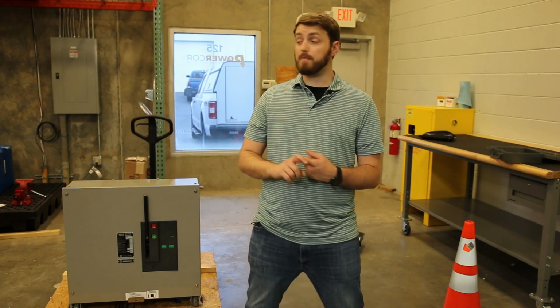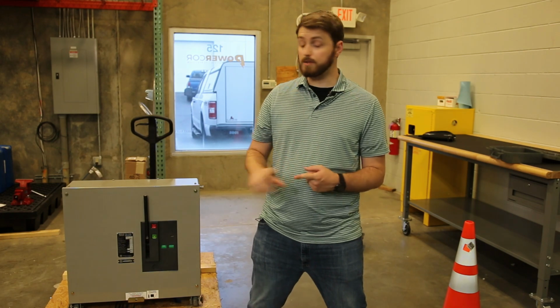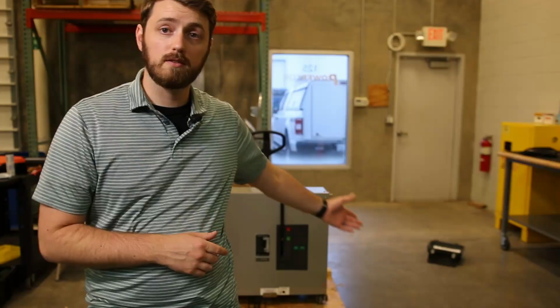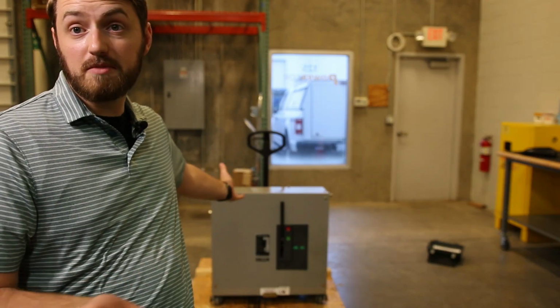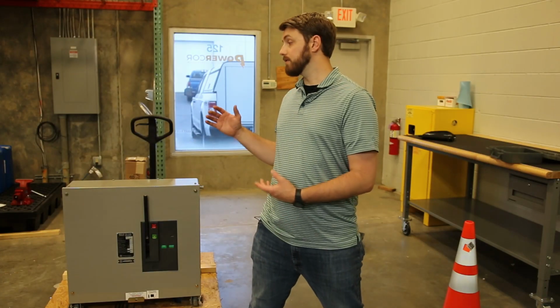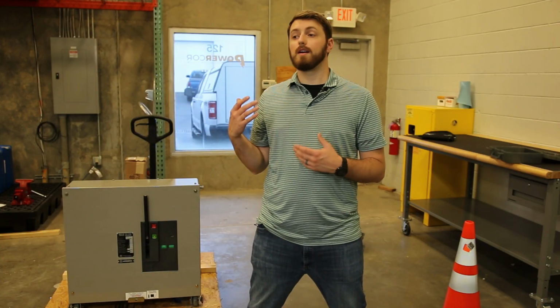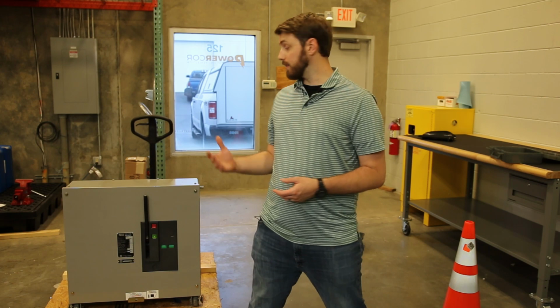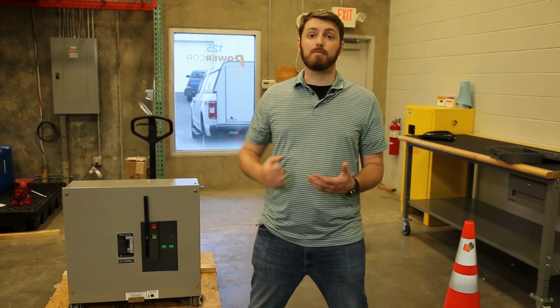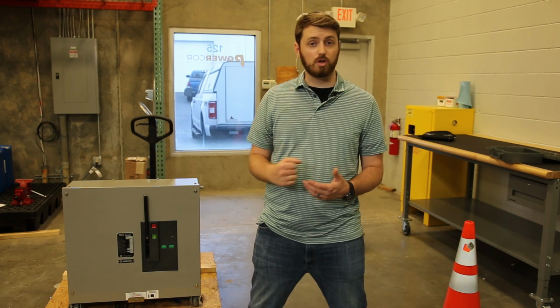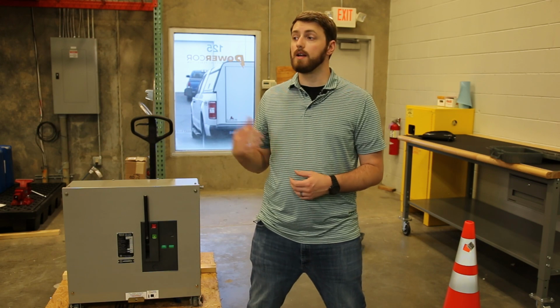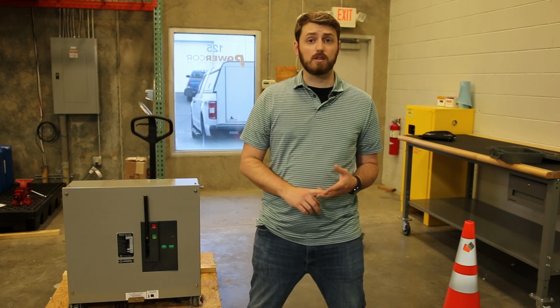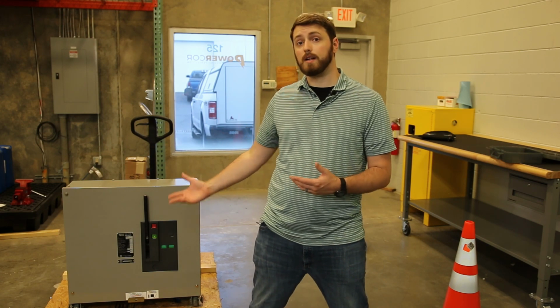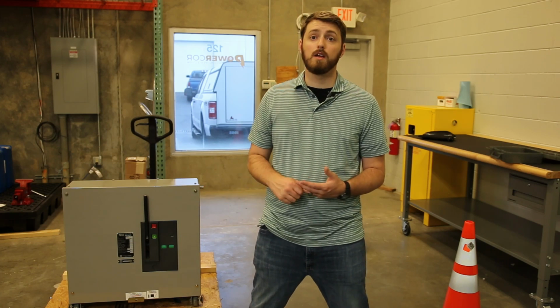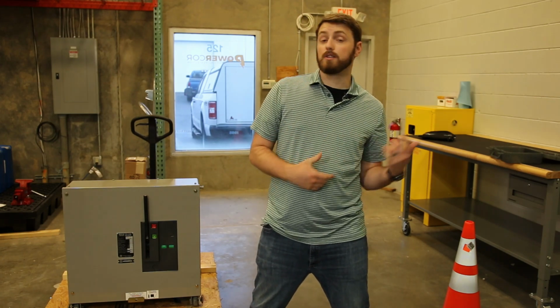The handful of them that are required, obviously we have to do the visual mechanical inspection. Look at it. Is it on fire? No, it's probably good. How does it look? Is there any dirt, water, signs of arcing, pitting, things like that? Does it mechanically operate? Can we manually charge, trip, close? We have to do the electrical operation. So if it has a charging motor, it has to work. So we're going to electrically charge it. We're going to electrically trip and close.